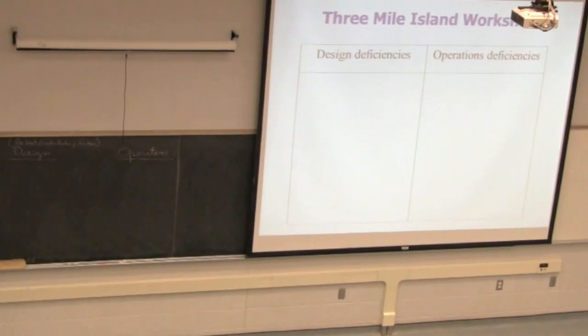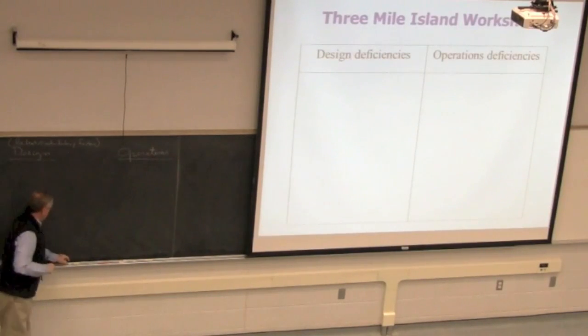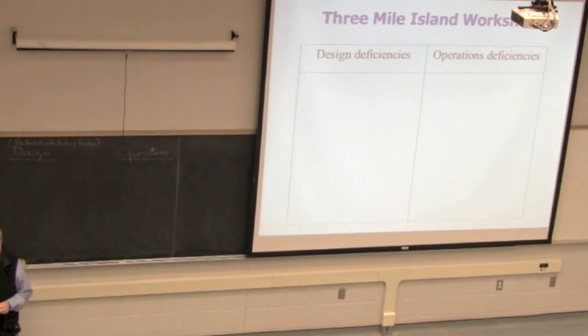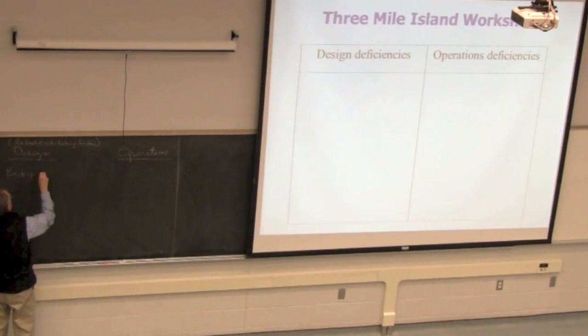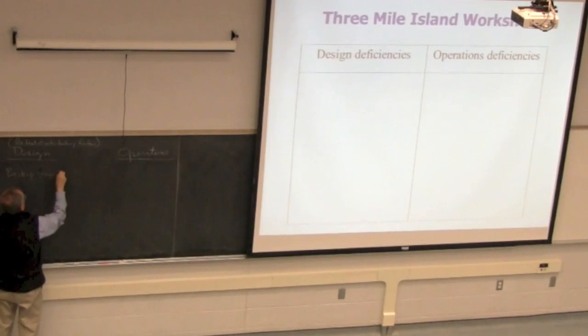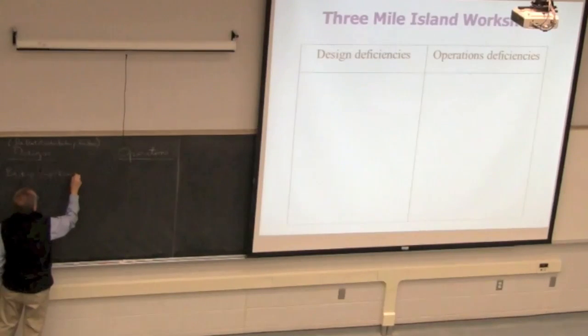Okay, I know you haven't had time to finish the whole thing, but let's share some ideas. Does anybody have a design issue? There is no pressure indicator to see over the back of the pump to show there's actually flow. Okay, so the backup. There's no measurement, right? Yeah.